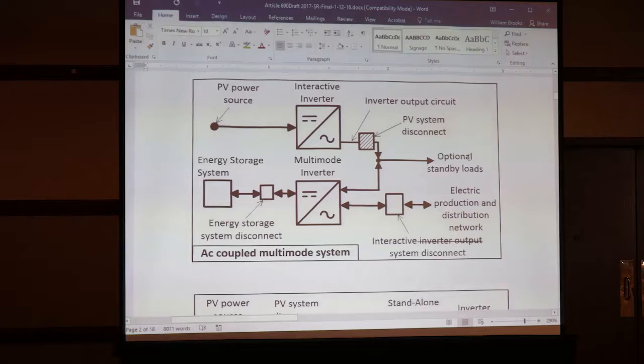So here's our optional standby loads. So it can't be on this side of the optional standby loads, because then the loads would be part of the PV system, and that's not allowed anymore. And then your energy storage system is the only thing on the DC side of this particular example.